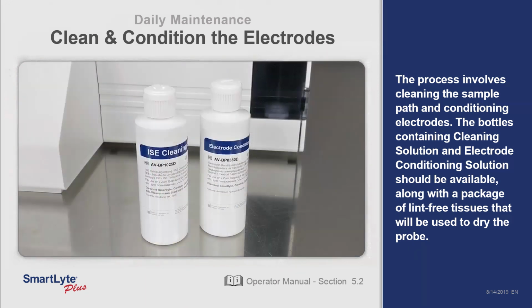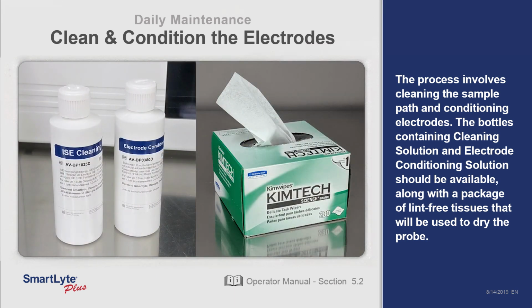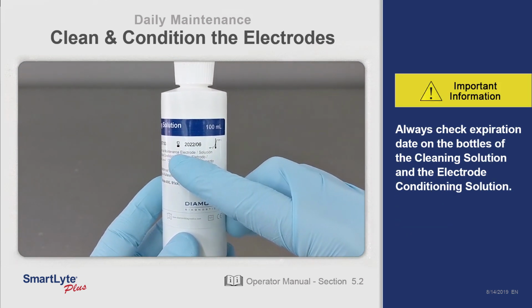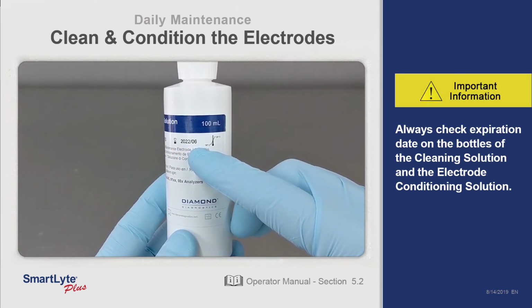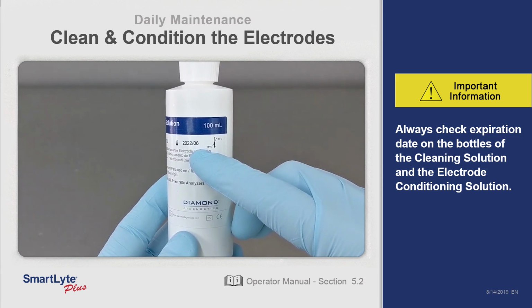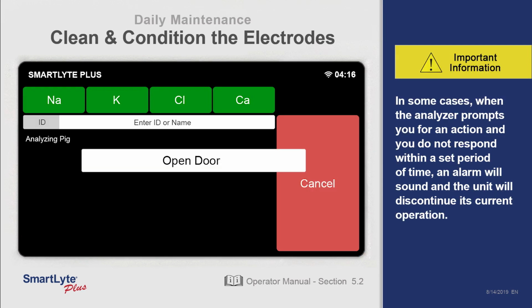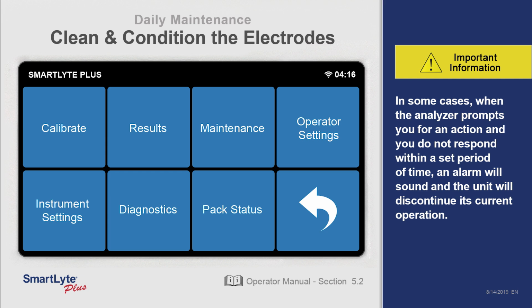The bottles containing cleaning solution and electrode conditioning solution should be available along with a pack of lint-free tissues that will be used to dry the probe. Always check the expiration date on the bottles of the cleaning solution and the electrode conditioning solution. In some cases, when the analyzer prompts you for an action and you do not respond within a set period of time, an alarm will sound and the unit will discontinue its current operation.